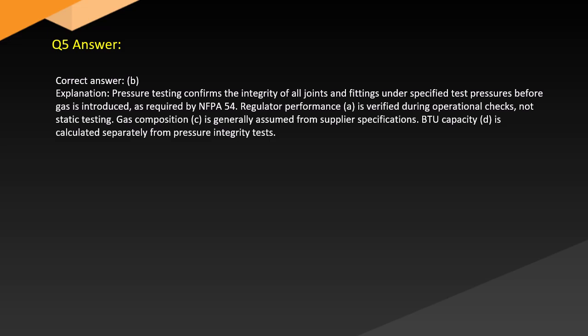Answer. Correct answer: B. Explanation. Pressure testing confirms the integrity of all joints and fittings under specified test pressures before gas is introduced, as required by NFPA 54. Regulator performance (A) is verified during operational checks, not static testing. Gas composition (C) is generally assumed from supplier specifications. BTU capacity (D) is calculated separately from pressure integrity tests.